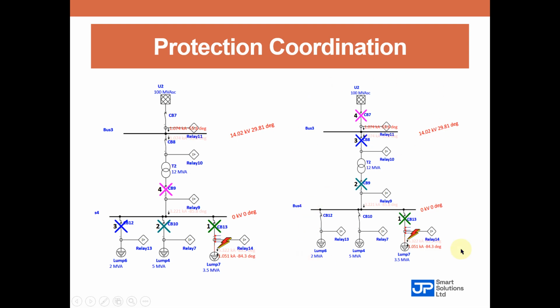We have the same system and then the same location of faults. The first breaker to open is circuit breaker number 13. The second breaker to open is circuit breaker number 9. The third breaker to open is circuit breaker number 8. And the fourth breaker to open is circuit breaker number 7, which is the source. So, in your own perspective, between these two systems, which is more coordinated? Which is coordinated, which is not coordinated, or which is partially coordinated and which is properly coordinated, or are both not coordinated?